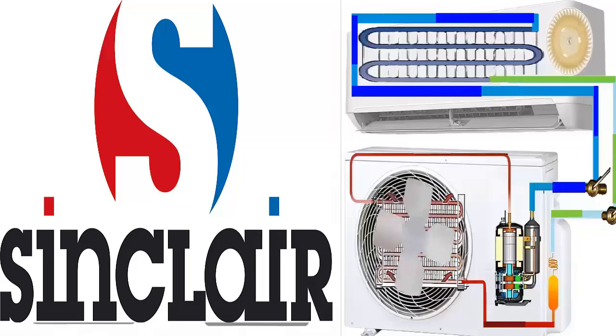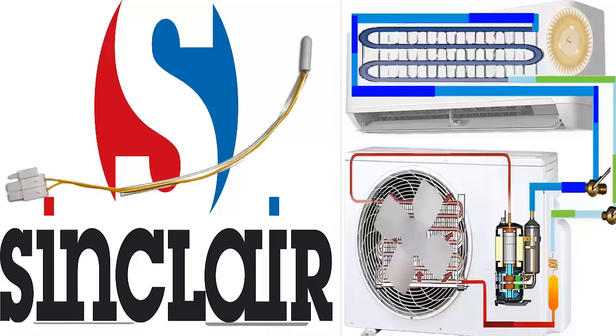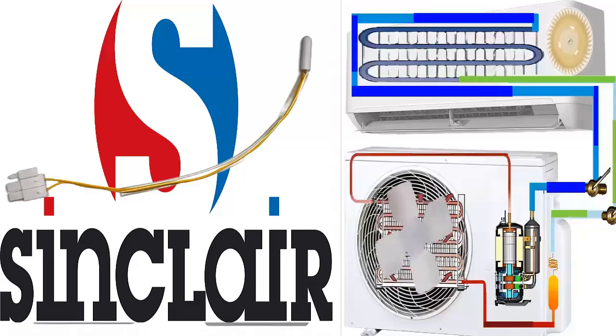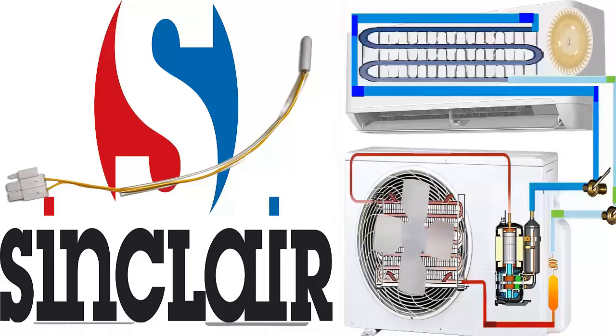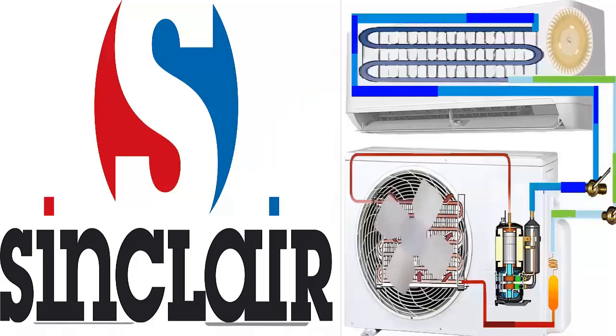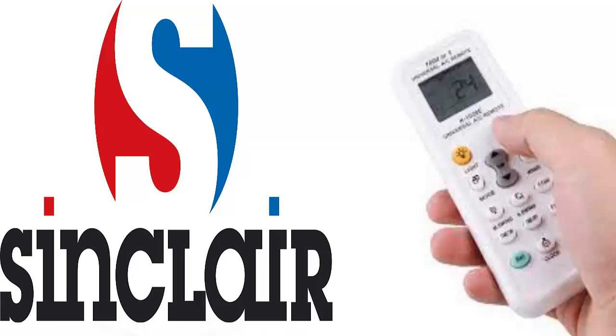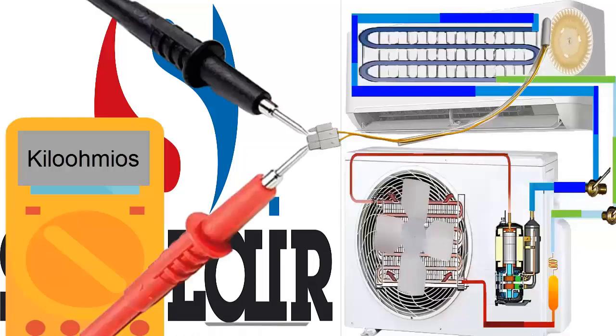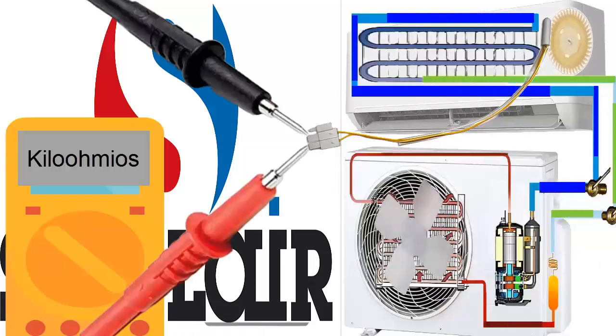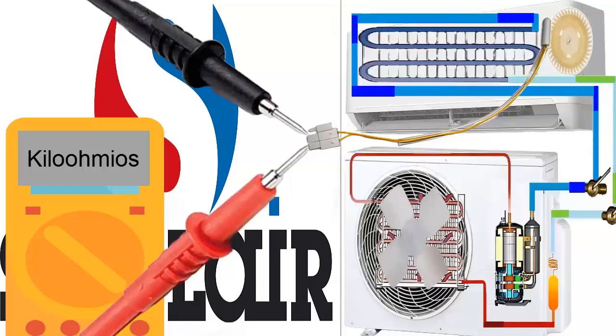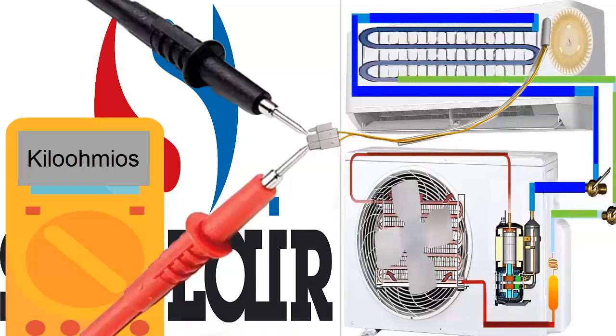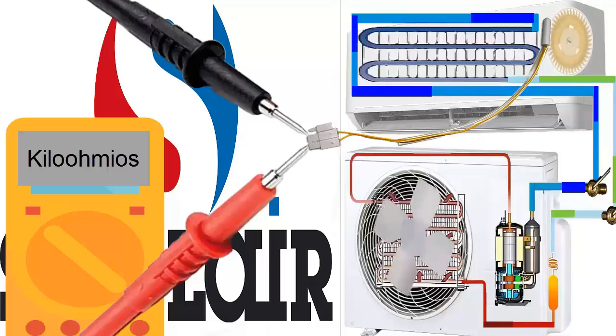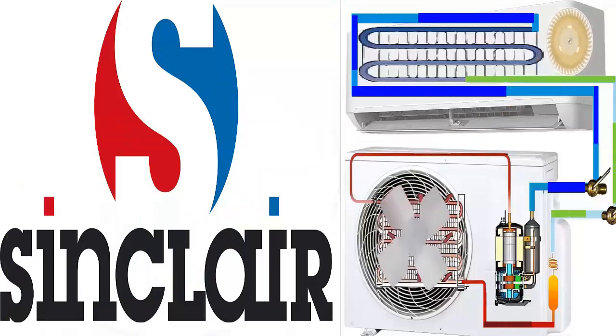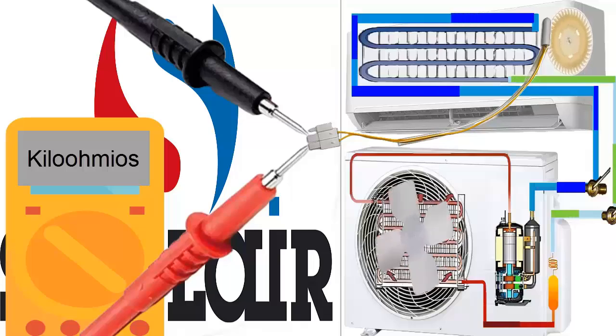5. Disconnect and reconnect the sensor. Clean the connections if necessary. 6. If the error persists, turn off the unit, disconnect the sensor, and measure its electrical resistance with a multimeter on the kilo-ohm scale. The measured value should never be 0 or infinite. If it is, replace the sensor.